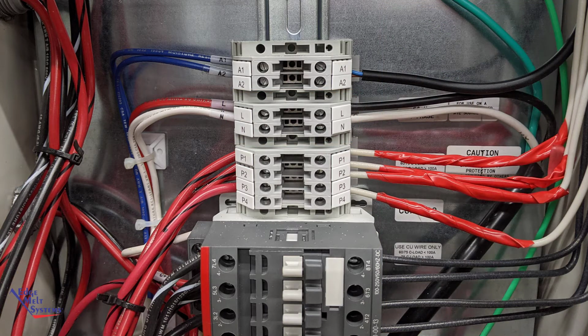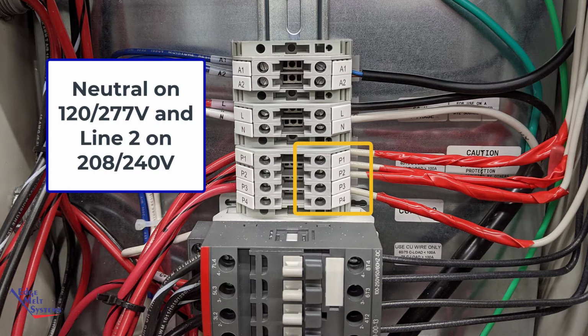For the purpose of this demonstration, the load side of the 4 EPD units are attached to the line side of the DC-AS4 digital controller at P1, P2, P3, and P4. Then load going out to the heat cables can be seen on the right side of the terminal block at P1, P2, P3, and P4. These legs are not switched and can be used for 120 volt through 277 volt hookup.